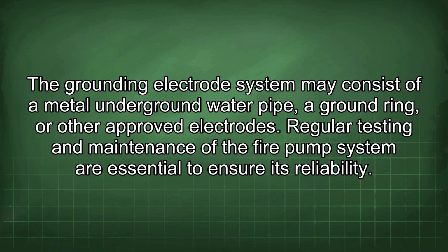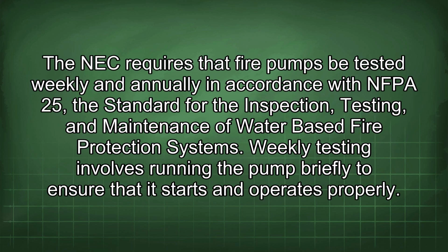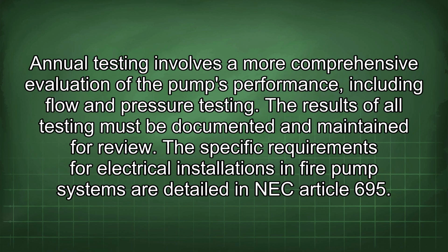Regular testing and maintenance of the fire pump system are essential to ensure its reliability. The NEC requires that fire pumps be tested weekly and annually in accordance with NFPA 25, the standard for the inspection, testing, and maintenance of water-based fire protection systems. Weekly testing involves running the pump briefly to ensure that it starts and operates properly. Annual testing involves a more comprehensive evaluation of the pump's performance, including flow and pressure testing.